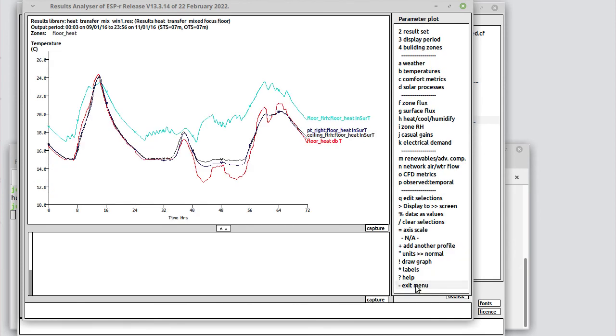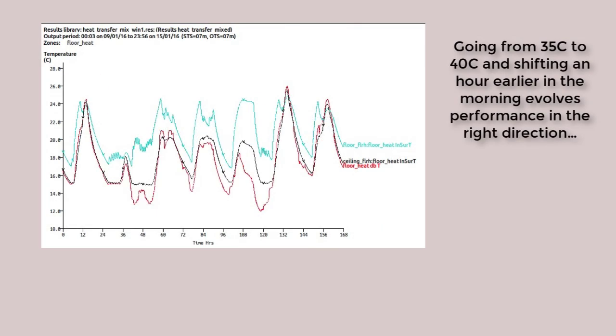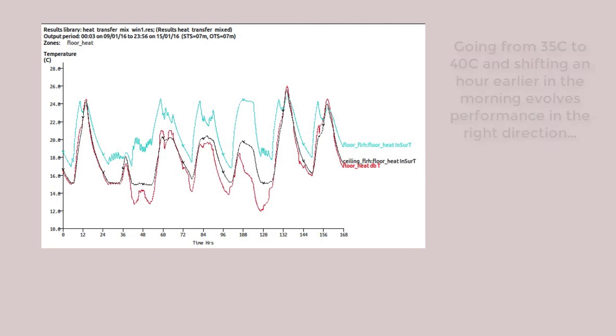I would say that a low temperature floor heating system is not doing terribly well for that time of year and with temperatures of, say, minus 12 degrees outside. Therefore, we could consider two possible options. One is to shift the start of the heating period earlier. Maybe it needs to be five o'clock in the morning in order to get us a decent ramp up in temperatures. Maybe we need to go to 40 degrees for the working fluid. Both of those would simply require small changes in the control law to enable. And then we could go and explore that. The result would then be knowledge about what kind of working temperature might actually be appropriate. What kinds of time delays are we noticing in the model? What kinds of control?